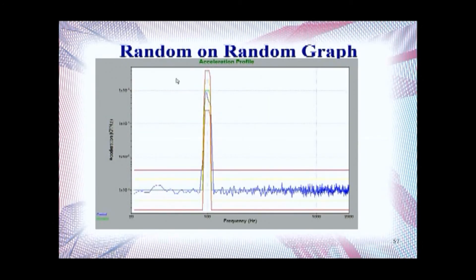Here is an example of a Random on Random vibration graph. Once again, the vertical axis is expressed in power spectral density, and the horizontal axis is expressed in frequency. Here you have your base random vibration curve, which is a flat line, and up here you have your fixed bandwidth random vibration, which is superimposed on top of the random vibration base.